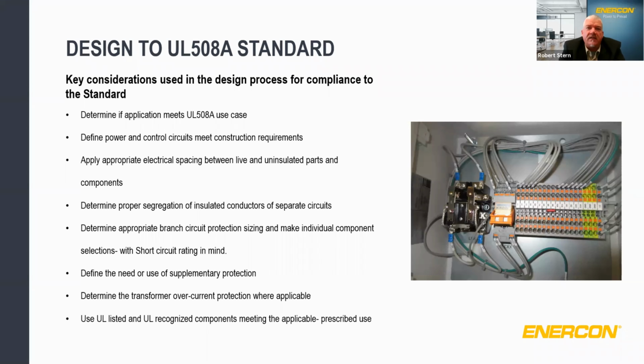You're going to want to define the branch circuit protection so that all of your loads and equipment are properly protected. You're going to have to determine whether or not you need supplementary protection. For example, if you have some internal controls that you need to protect separately from power controls, whether or not the transformer that you're using is properly spec'd, as well as the conductors going to and from the transformer. And you're going to want to pick UL listed or UL recognized components to make sure that your panel's in compliance where applicable. Next slide.